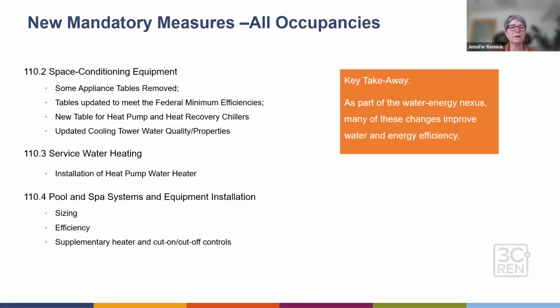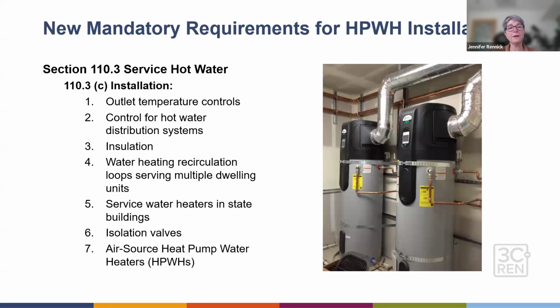So under those mandatory measures for all occupancies, there have been some updates on space conditioning equipment, the service water heating, pool and spa equipment. The big takeaway is that they're trying to include more easy to follow mandatory measures to kind of clean up the code for what we were seeing as maybe being installations that weren't up to par to really achieve the energy efficiency that our state wants to achieve. Today, we're just going to look at the service water heating as an example. And then under that service water heating category, there's all kinds of things to take a look at in terms of temperature controls and the insulation and recirculation loops and isolation valves, etc. But there's a brand new section specifically for air source heat pump water heaters, section 7.